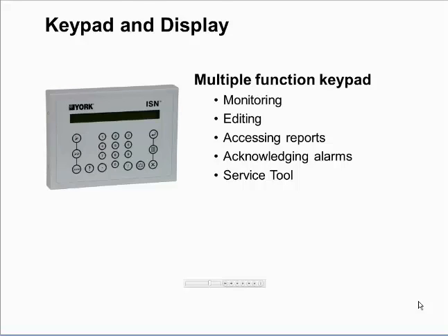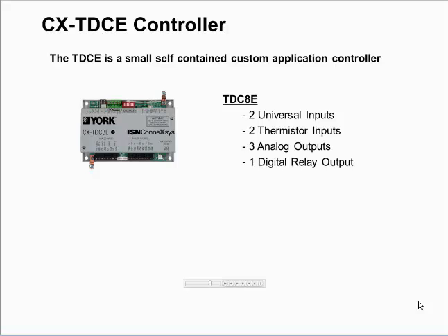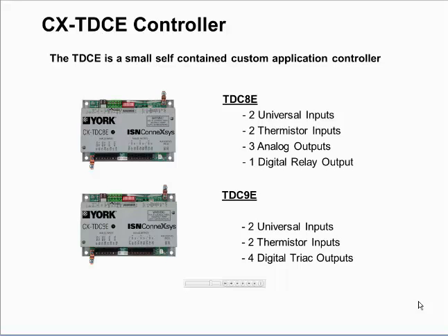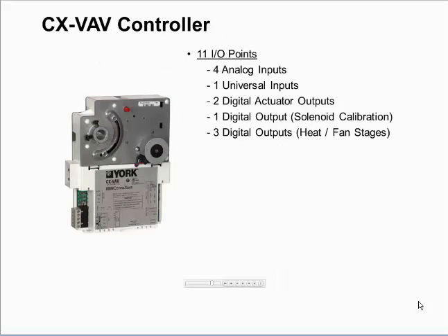The TDC is a small self-contained custom application controller. The TDC-8E has 2 universal inputs, 2 thermistor inputs, 3 analog outputs, and 1 digital output. The TDC-9E has 2 universal inputs, 2 thermistor inputs, and 4 digital TRIAC outputs. The CXVAV controller has 11 I/O points, 4 analog inputs, 1 universal input, 2 digital actuator outputs, 1 digital output, and 3 digital outputs for heat fan stages. Non-volatile flash memory for backup of all application data. The RS-485 network port is used to connect to other ISN controllers.